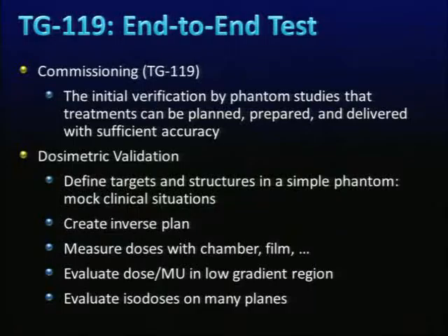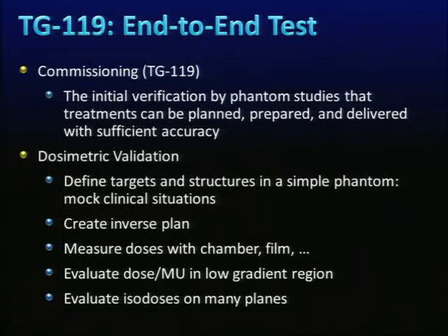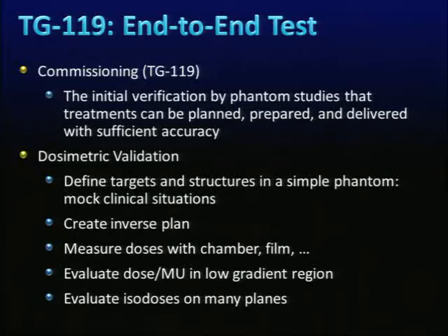Moving to the end-to-end test: once basic MLC and VMAT testing is done, you test under real conditions. TG-119 recommends dosimetry validation by defining test targets and structures, creating mock clinical cases, making inverse plans, measuring dose with chamber, film, or other devices, and evaluating dose per MU in high- and low-gradient areas, as well as isodose in multiple planes.